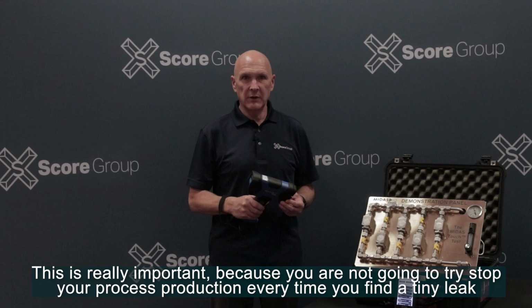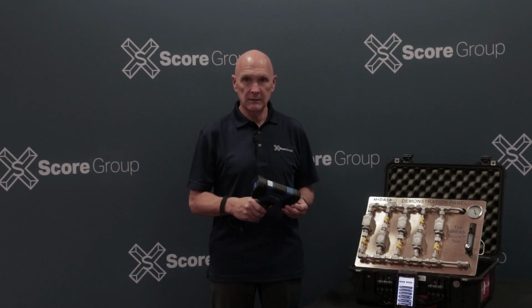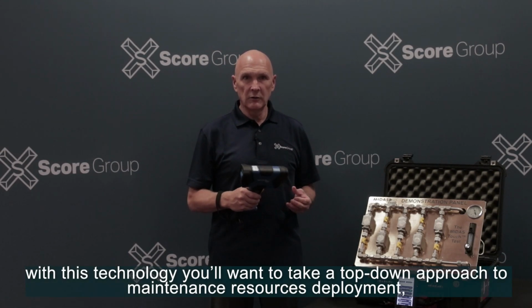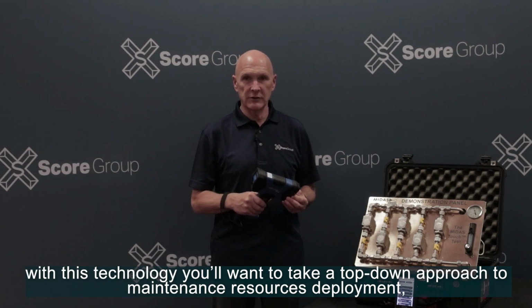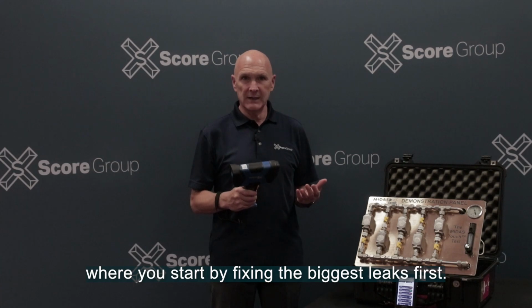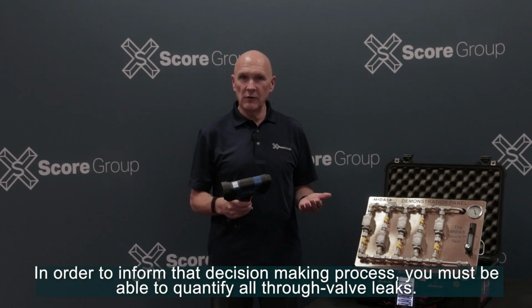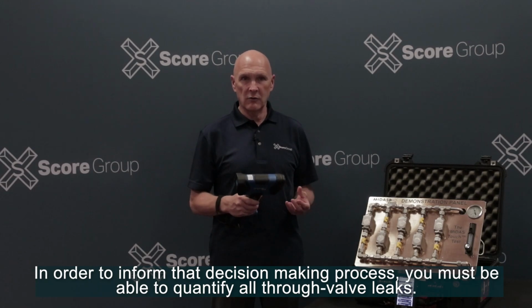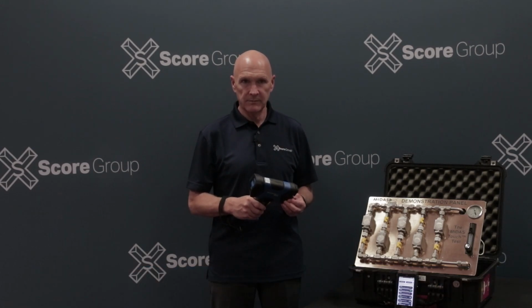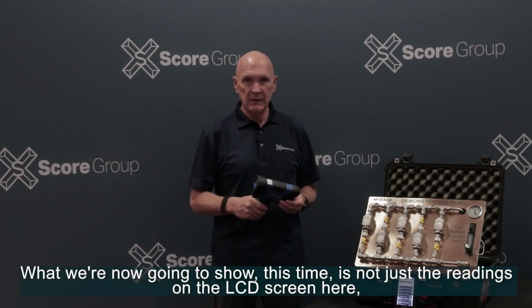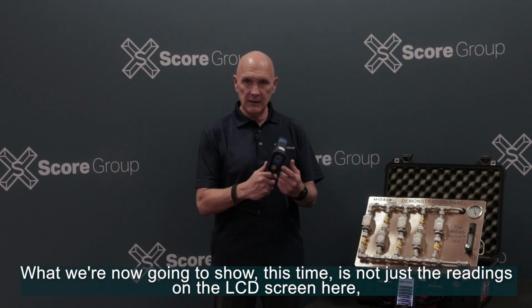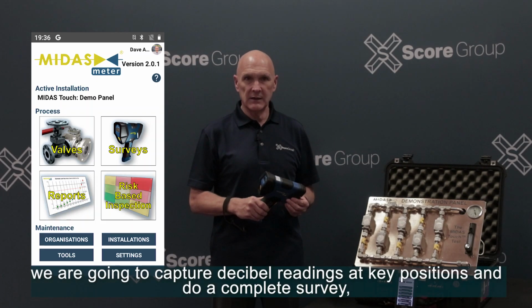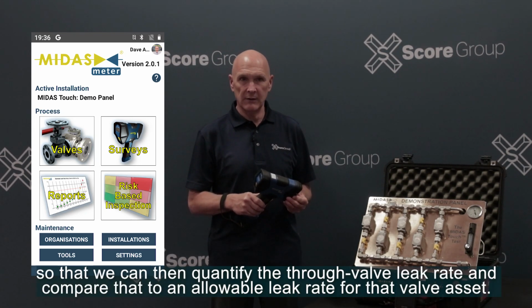This is really important because you're not going to try and stop your process production every time you find a tiny leak. With this technology, you'll want to take a top-down approach to maintenance resources deployment, where you start by fixing the biggest leaks first. In order to inform that decision-making process, you must be able to quantify all through-valve leaks. What we're now going to show this time is not just the readings on the LCD screen here, but we're going to capture decibel readings at key positions and do a complete survey so that we can then quantify the through-valve leak rate and compare that to an allowable leak rate for that valve asset.